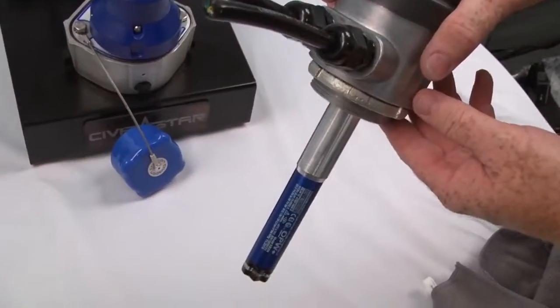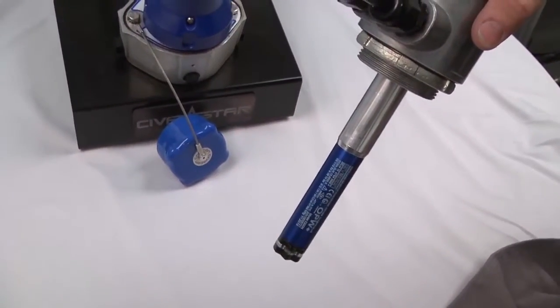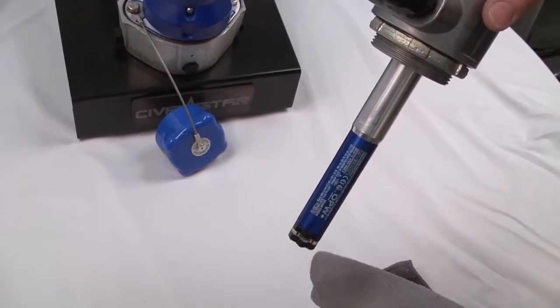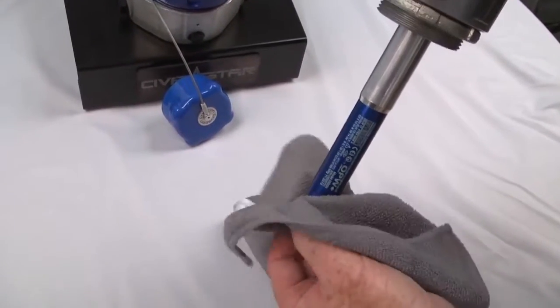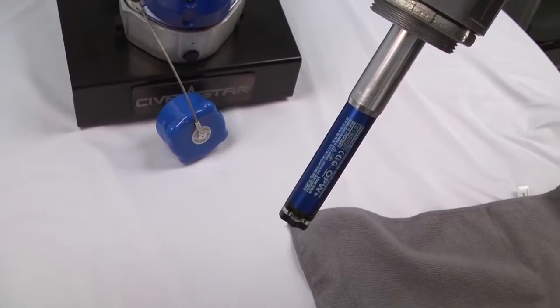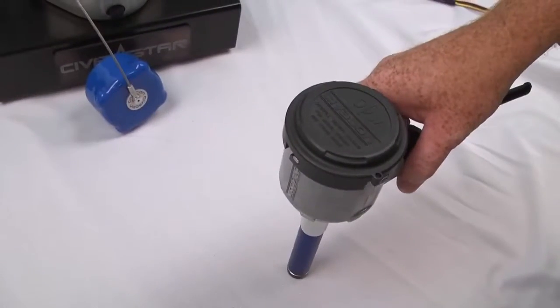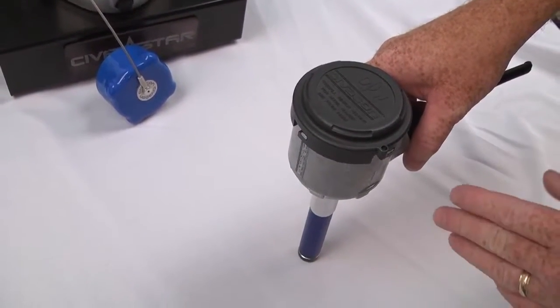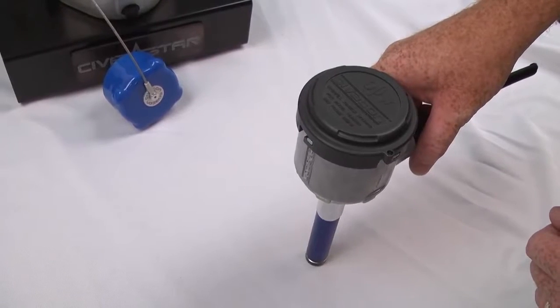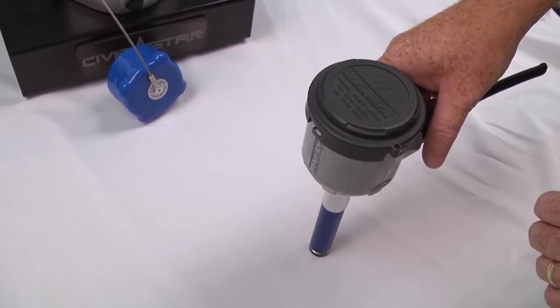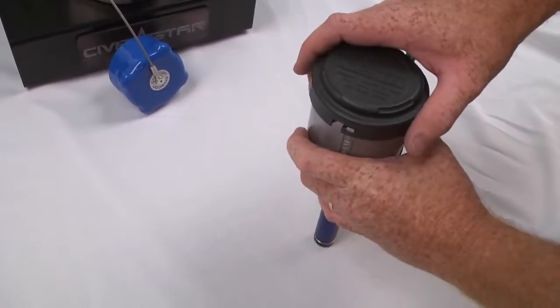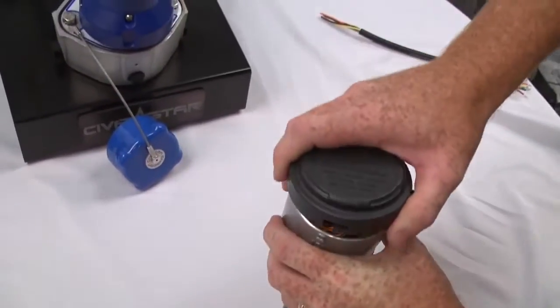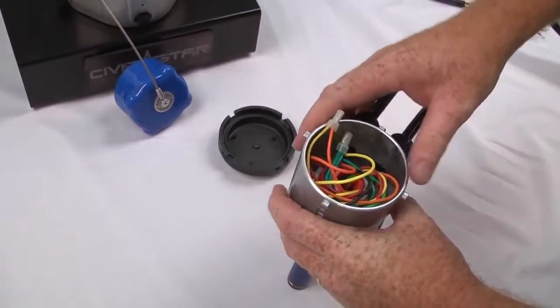The first step you want to do is to ensure that the probe is dry on the end of the prism. Just take a dry, clean rag, wipe it off, and see if that clears out your faults at your tester. Now, if you've determined that the probe is essentially dry and it's still showing a fault state, you'll need to start inspecting your wire connections. Start by removing the housing cap on the problematic probe.